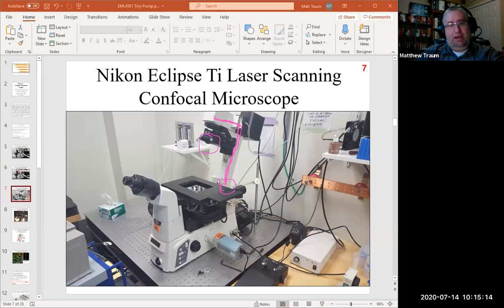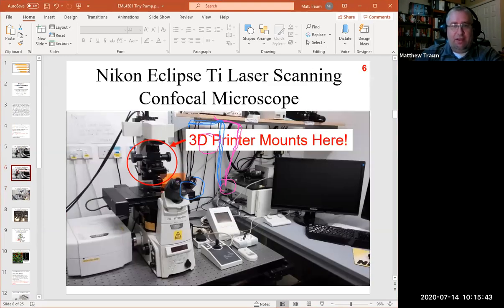But when you go to actually use the microscope, let me use a different color. This arm rotates around the hinge and snaps back into place, so it's vertical, and the dovetail sits out cantilevered above the optics, which are down here. If I jump to another image, there we go. Now you can see that the arm is in place, and the dovetail is sitting out cantilevered above the optics. Provided everything is calibrated correctly, it is in the same plane as the table underneath, to address the question.